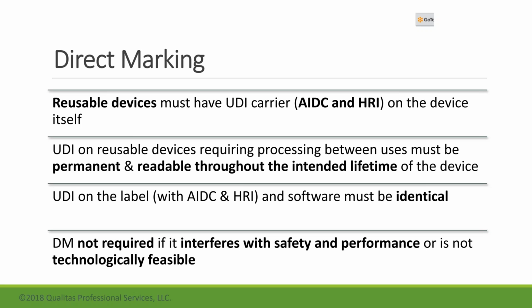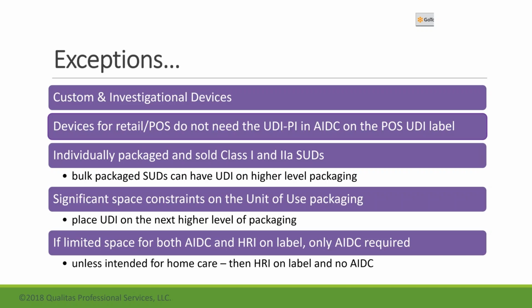Don't just say that, oh, this is going to interfere with the safety and performance. You have to have testing, and you have to have evidence to show that it's not safe or that it affects the performance of the device. So again, everything in regulatory and in medical devices and in life in general, we know that there are exceptions. And some of these exceptions that are called out in the MDR are related to custom and investigational devices. They do not need to have UDI or direct marking.